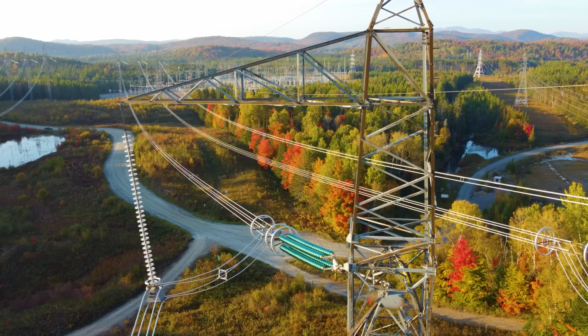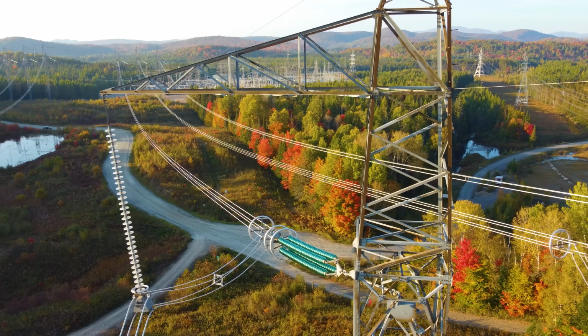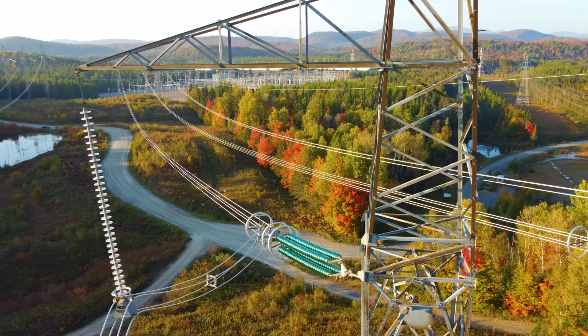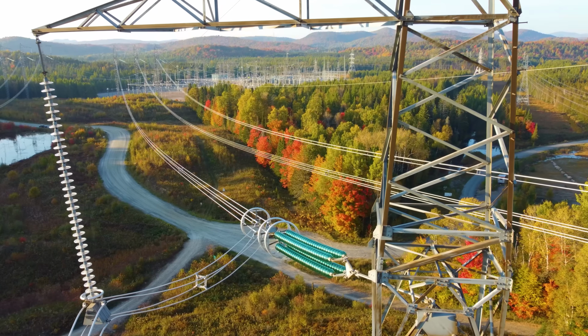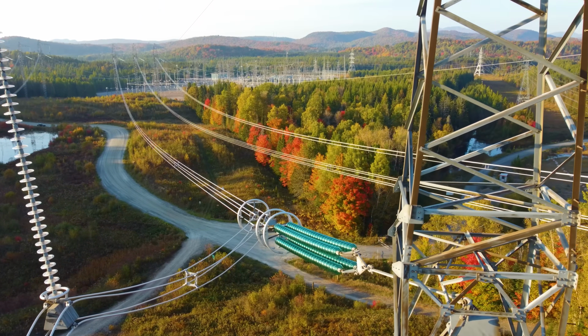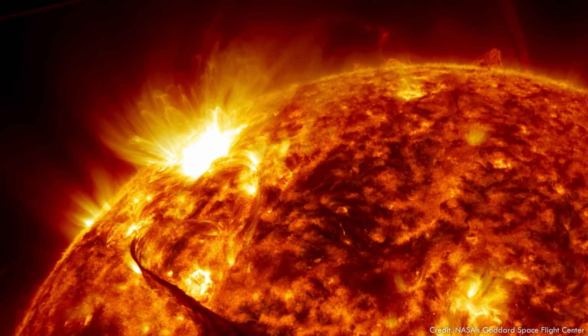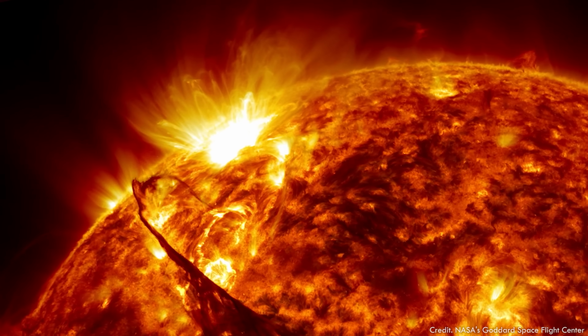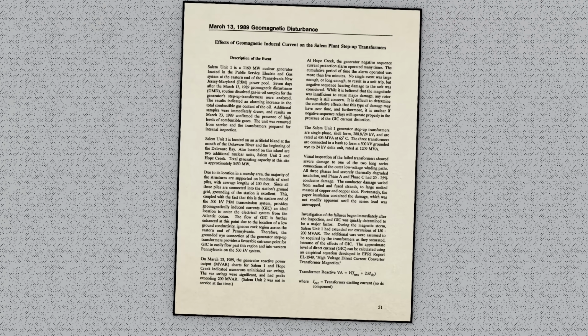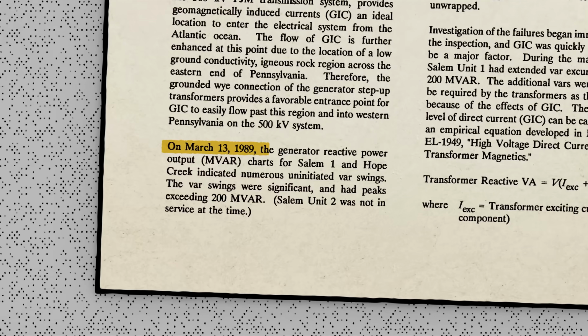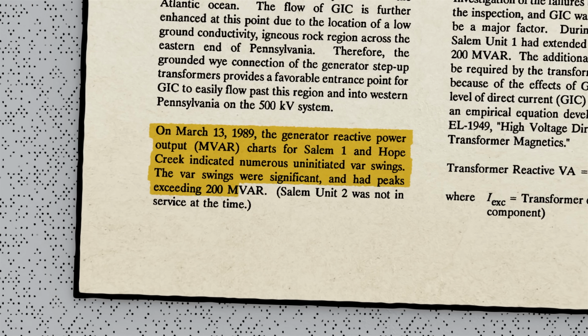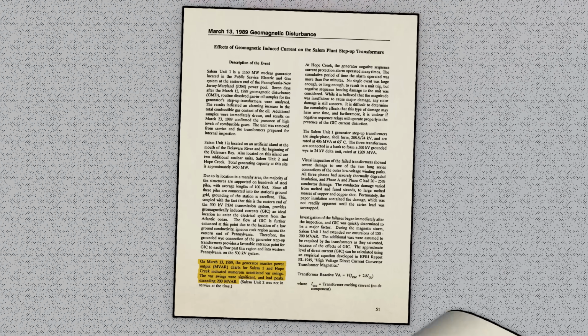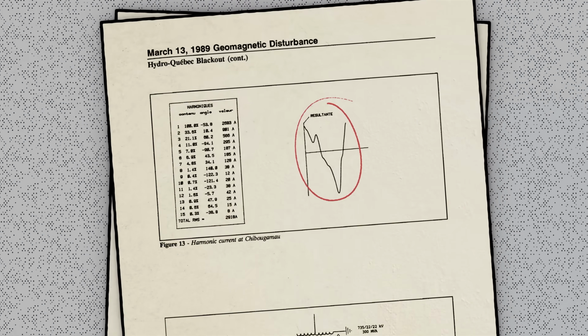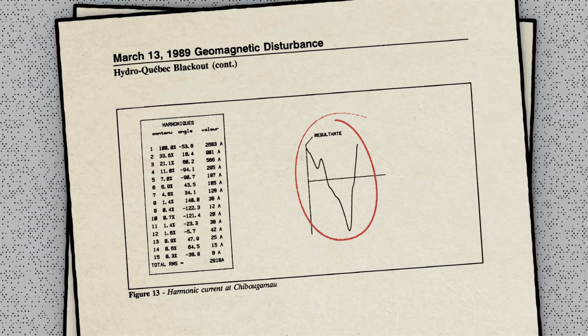The long transmission lines between the hydroelectric power plants in the north and the load centers in the south require careful control of the voltage to avoid instability, but the geomagnetic storm threw a wrench in the works. The induced currents in the transformers and along those transmission lines seriously increased the reactive power demand of the system. The resulting distortions in the voltage and current waveforms hadn't been considered when the equipment was installed.